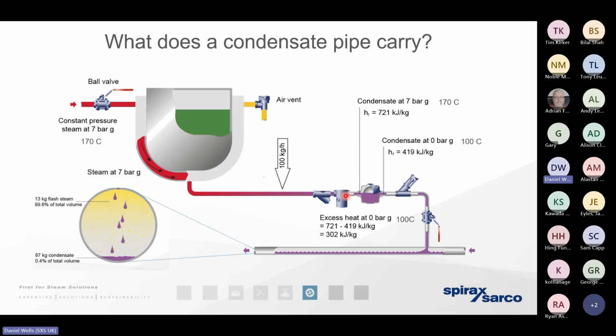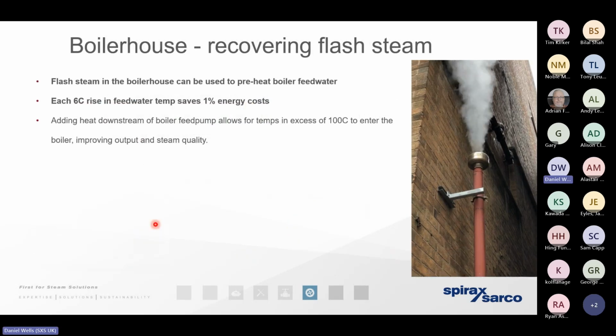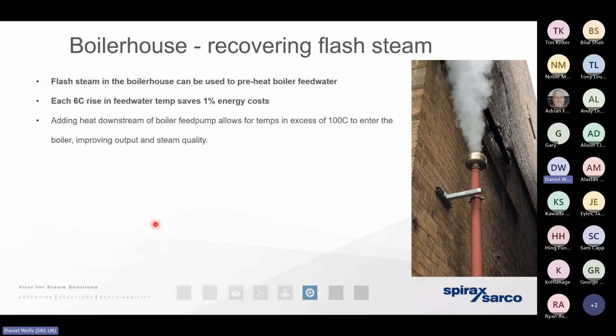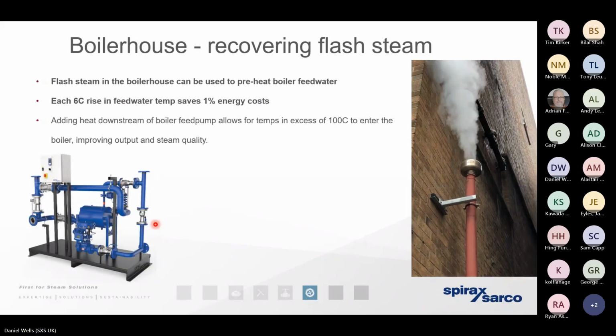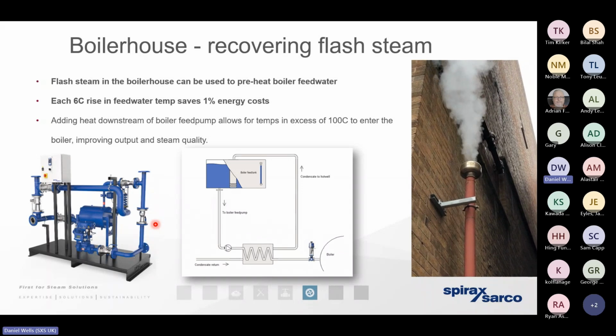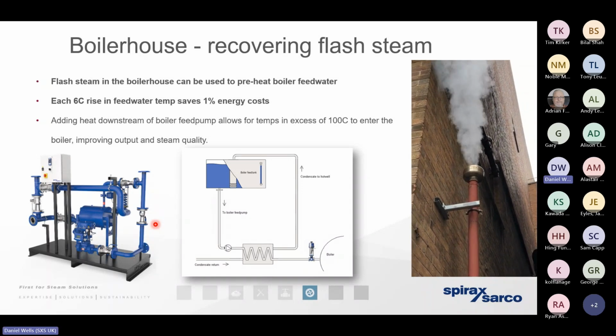So when the condensate depressurizes as it moves across the trap, that's when we're going to get that phase change in that rapid expansion. And that's when clients are going to be tempted to vent that expansion away to atmosphere in order to reduce the infrastructure cost and in order to minimize any damage that could be imparted by that expansion. The problem is we need to bear in mind that, yes, we're venting the expansion away, but there's a significant amount of heat energy that is also being lost.